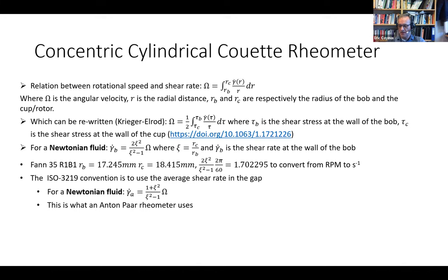For a scientific rheometer like an Anton Paar, the convention is not to use the shear rate at the bob but the average value across the gap. The conversion formula for Newtonian fluid is slightly different: (1 + ξ²) / (ξ² - 1) times omega. This conversion from rotational velocity to shear rate differs between instrument types — if a scientific rheometer gives you a shear rate, it is not necessarily the same as what you have for the Fann 35.